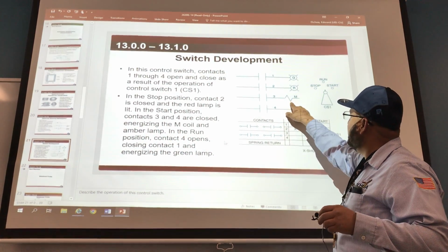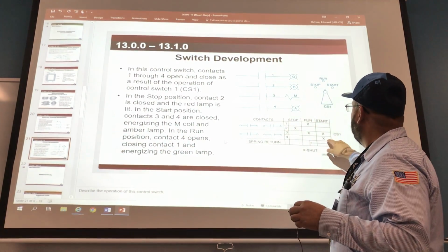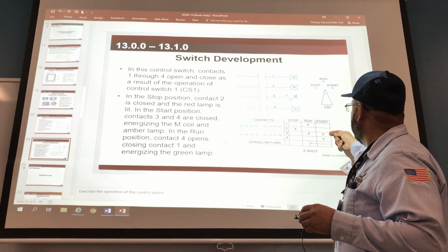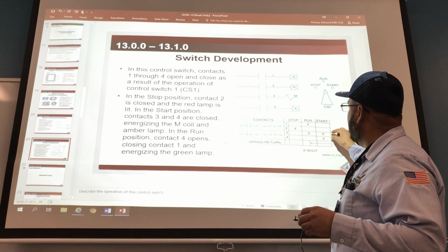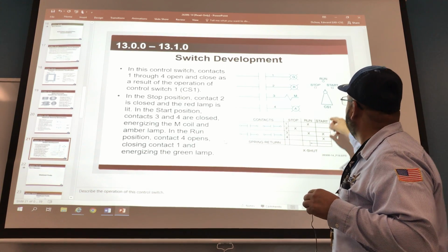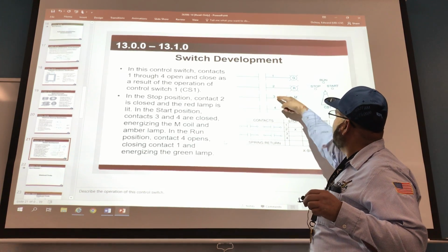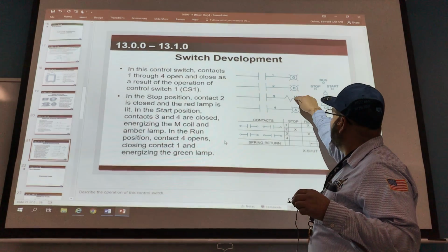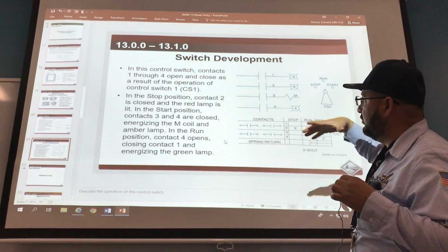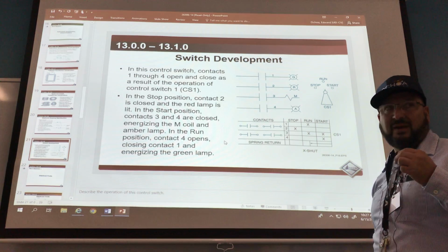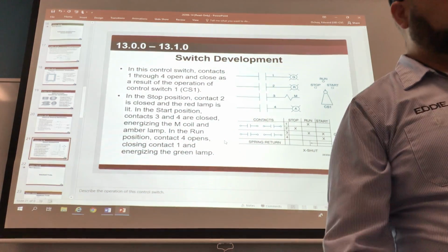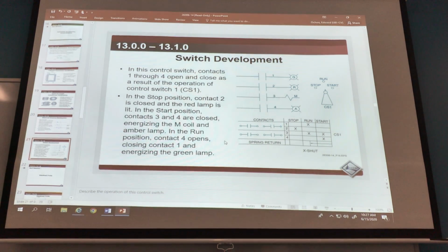1 and 3. It's a maintaining contact for a motor, right? If you hit start, then this is going to be started up. So now 3 and 4 will be closed. You put this to start. 3 and 4, the light will turn on. The maintaining contact will turn on, which allows current to go through the maintaining contact to run the motor, and it'll always be that way. Most motors of high capacity will be on this type of system.